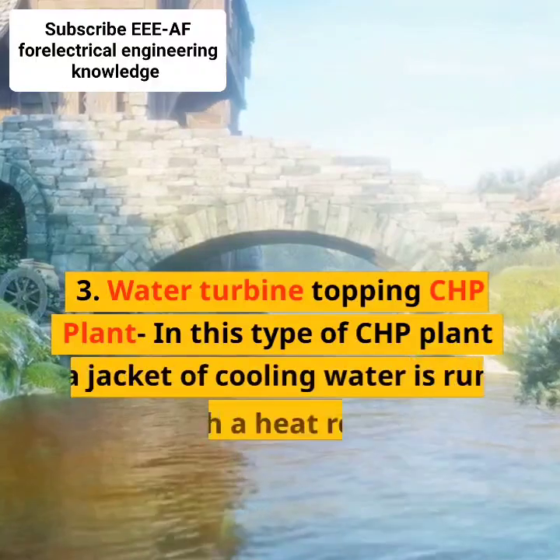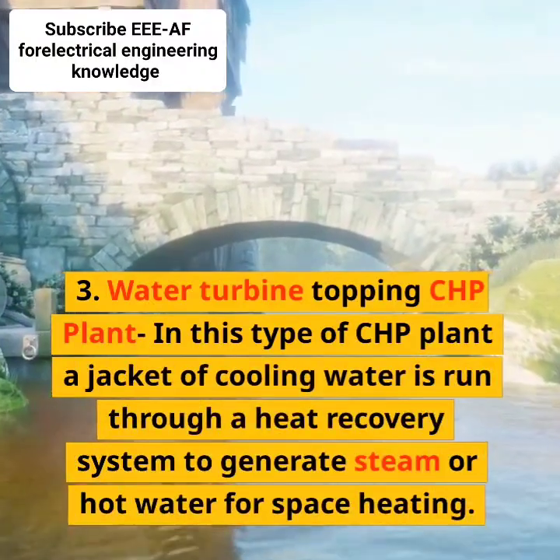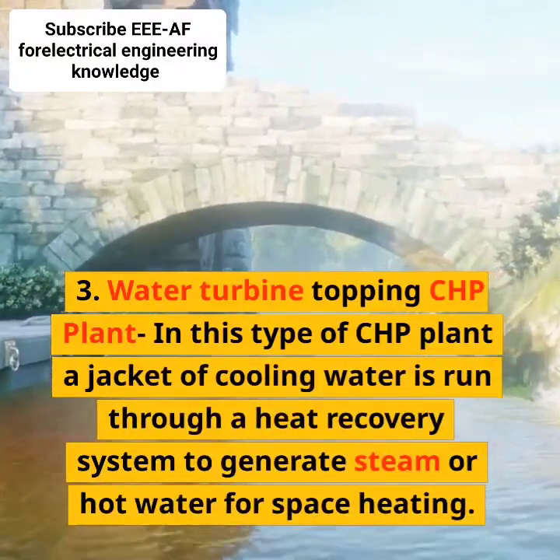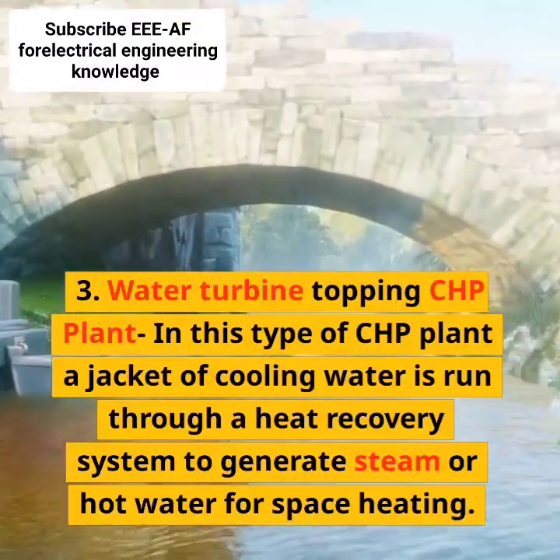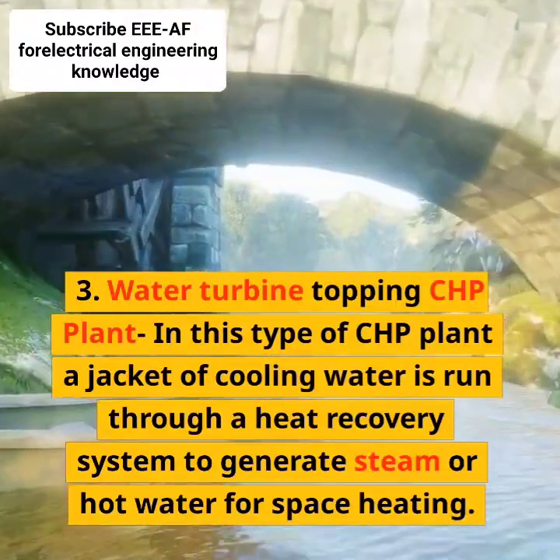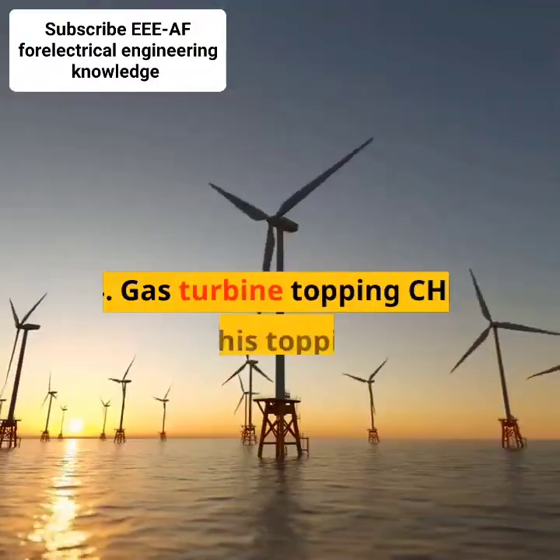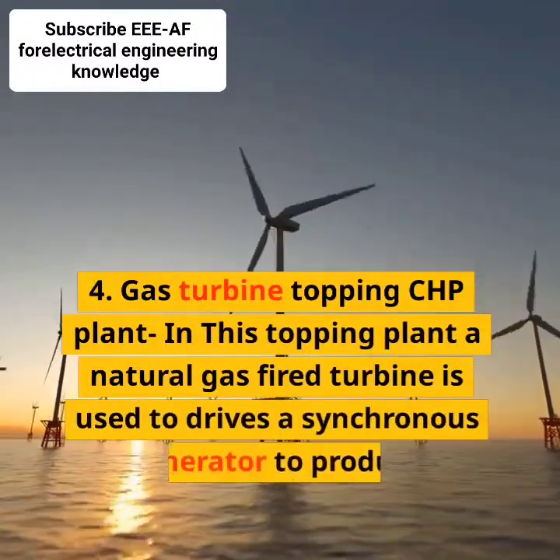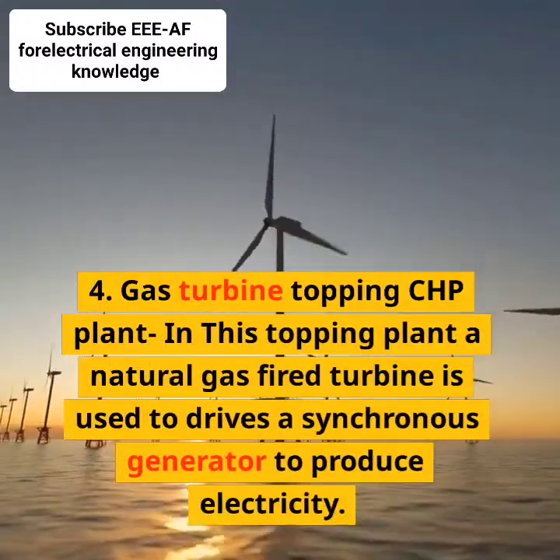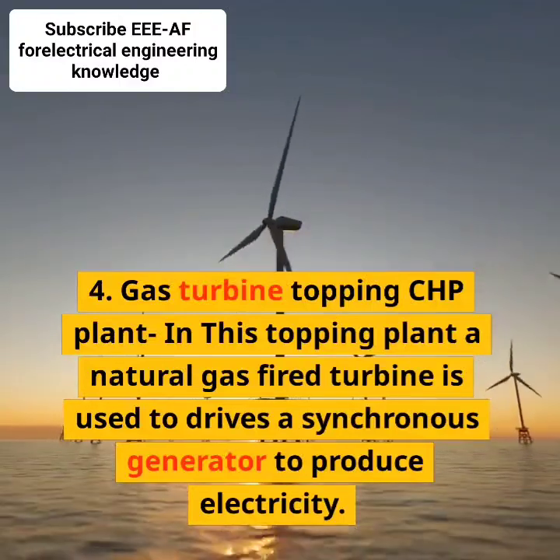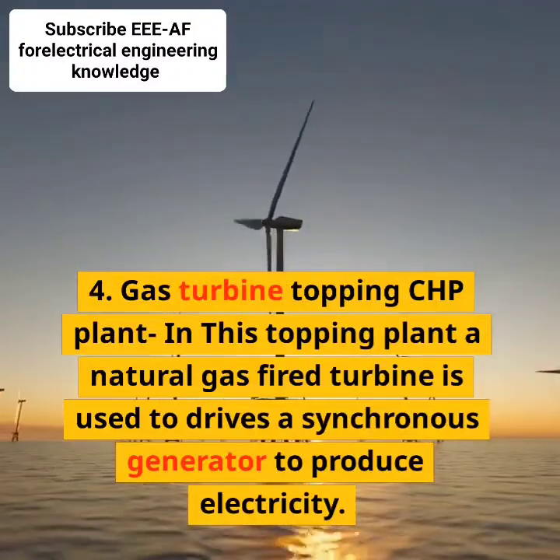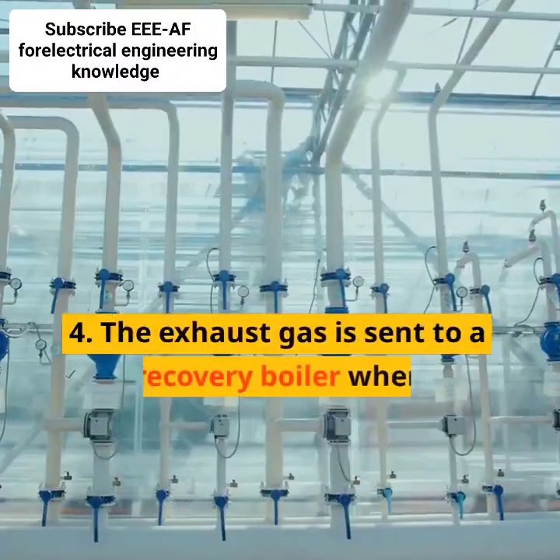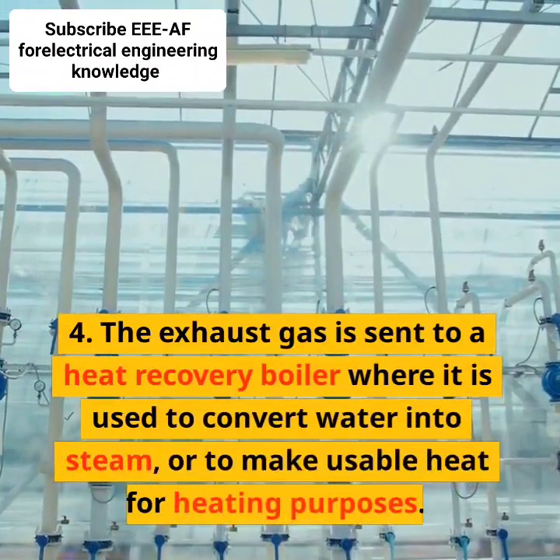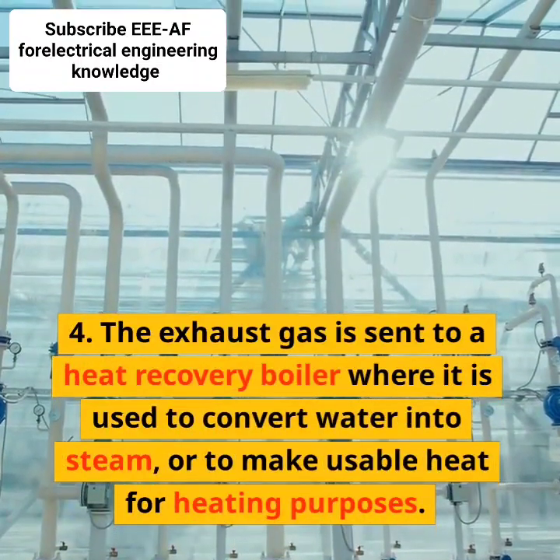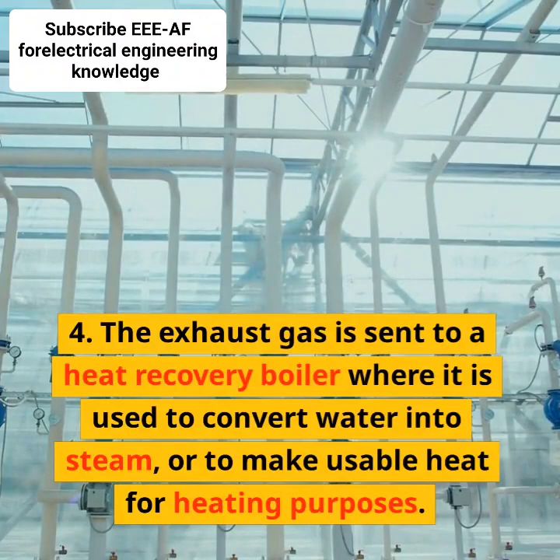3. Water turbine topping CHP plant. In this type of CHP plant, a jacket of cooling water is run through a heat recovery system to generate steam or hot water for space heating. 4. Gas turbine topping CHP plant. In this topping plant, a natural gas-fired turbine is used to drive a synchronous generator to produce electricity. The exhaust gas is sent to a heat recovery boiler where it is used to convert water into steam, or to make usable heat for heating purposes.